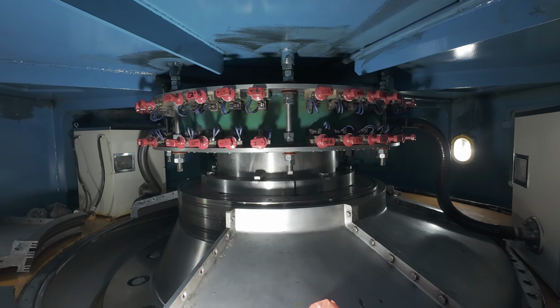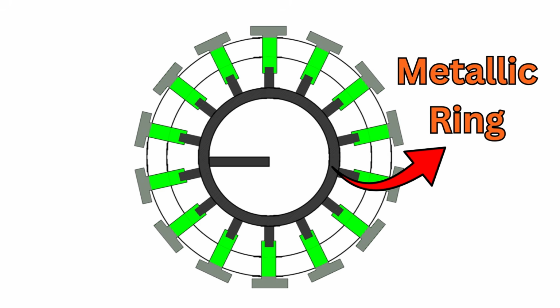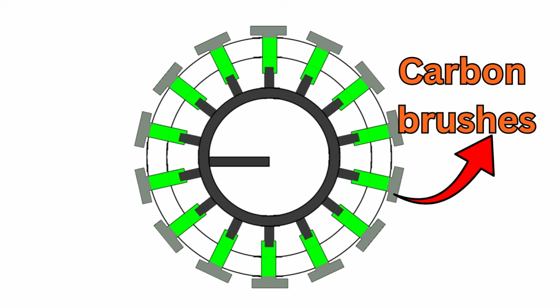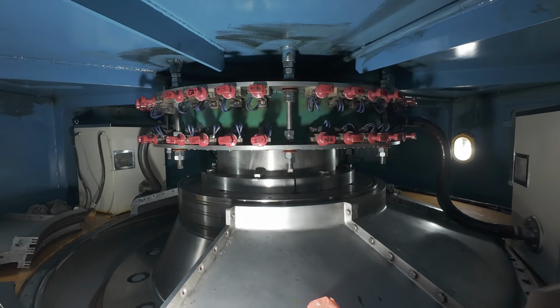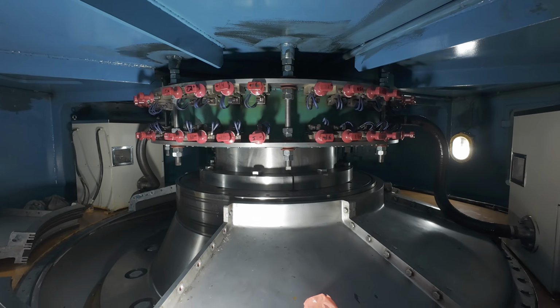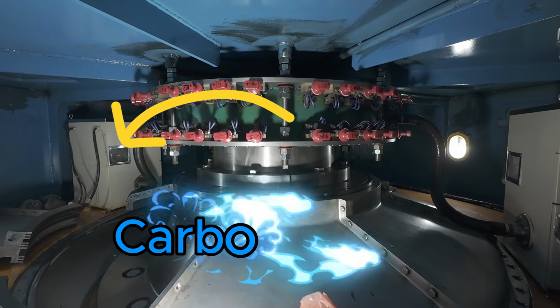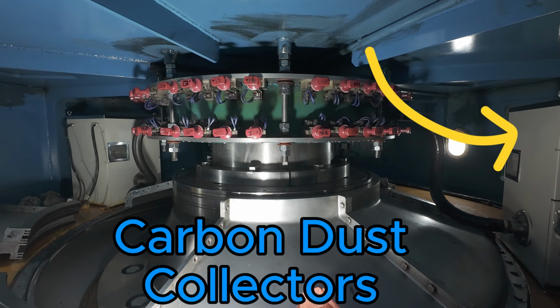And surprisingly, some of the most critical electrical connections inside the powerhouse are literally sliding contacts rubbing against a spinning ring every second. So inside a large generator, dozens of carbon brushes may operate simultaneously. These carbon brushes wear over time, so the generator has carbon dust collectors. Like here, you can see there are two carbon dust collectors installed in this unit.